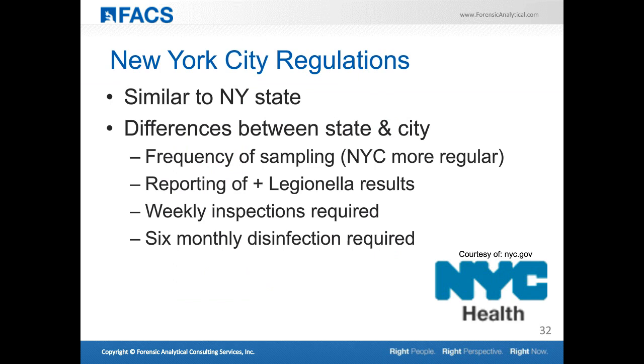New York City also implemented their own regulations, very similar to New York State, but there are some general differences. New York City requires more frequent sampling on a more frequent interval, and requires reporting of positive Legionella results to the Department of Public Health. Weekly inspections are required, and six-monthly disinfection with a written report detailing the disinfection procedures performed for cooling towers. Those are just some of the differences between the state and city regulations.